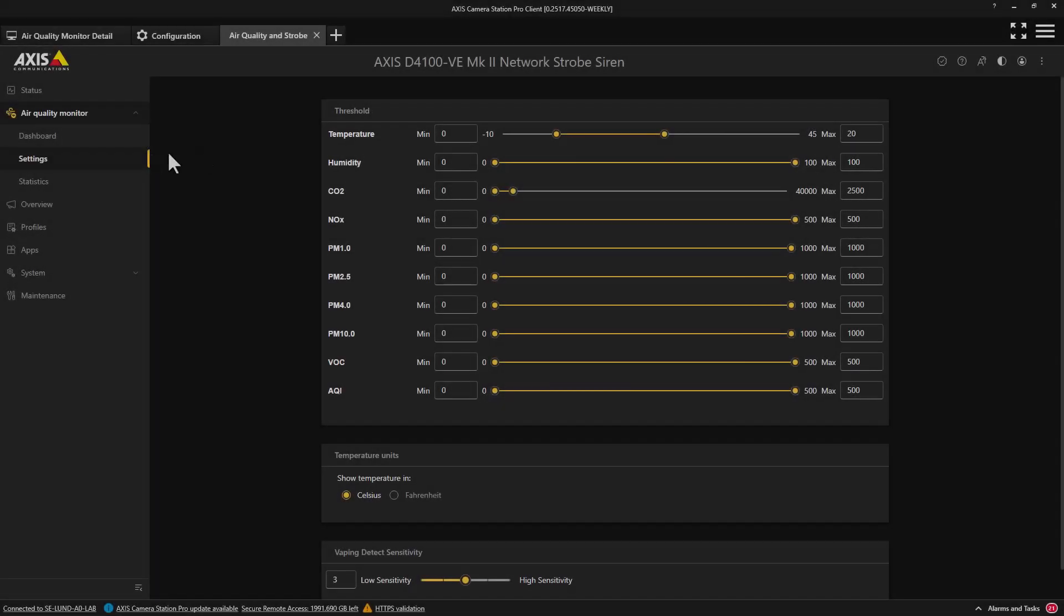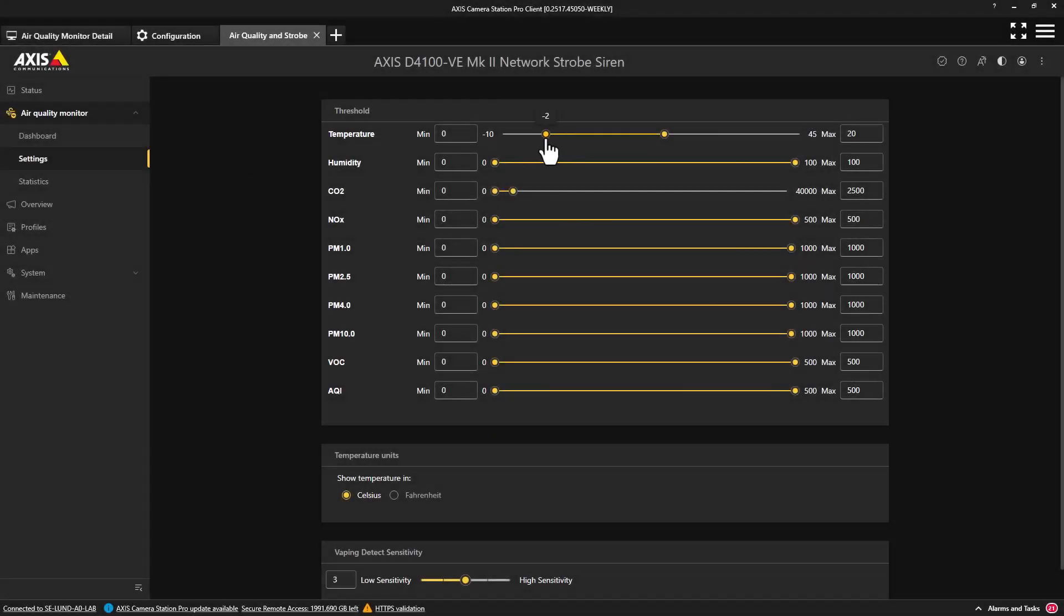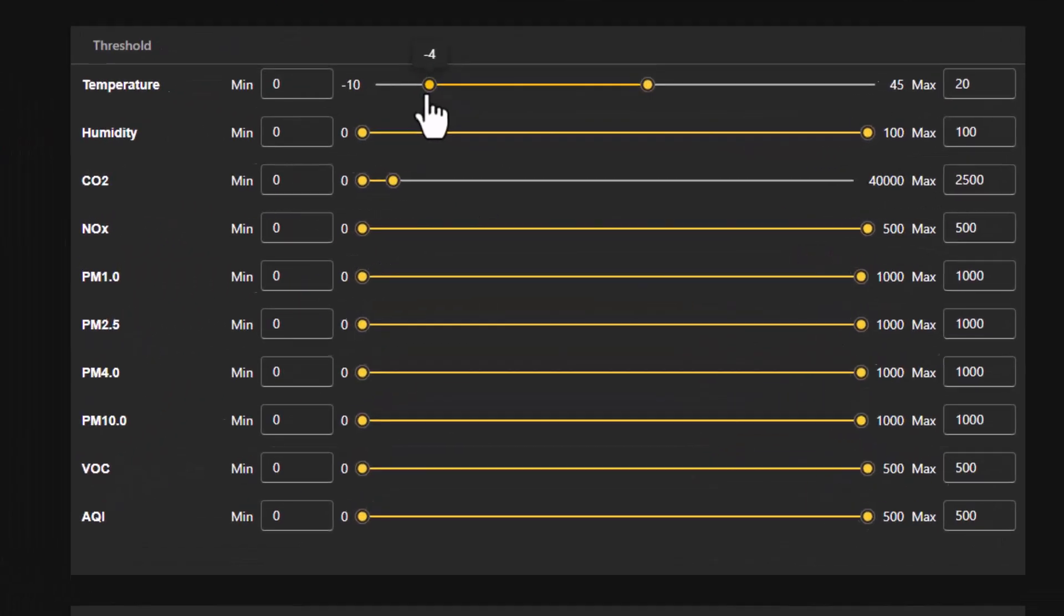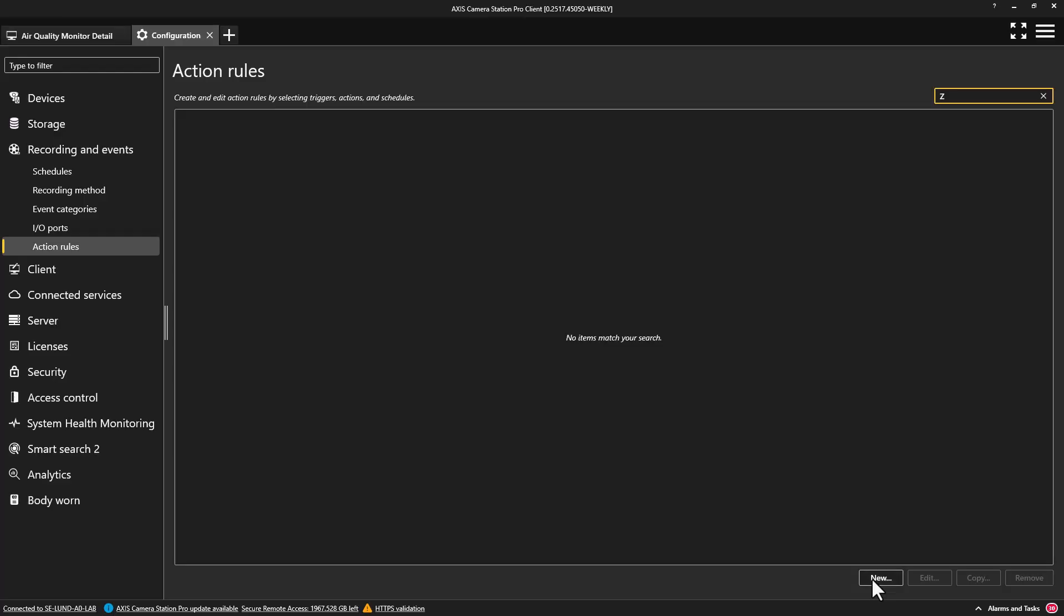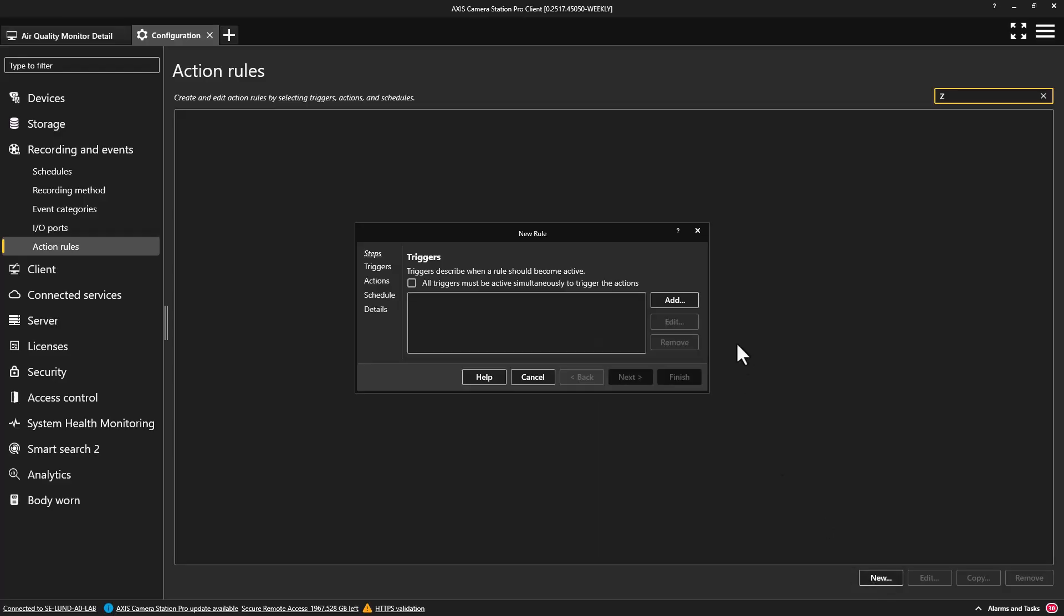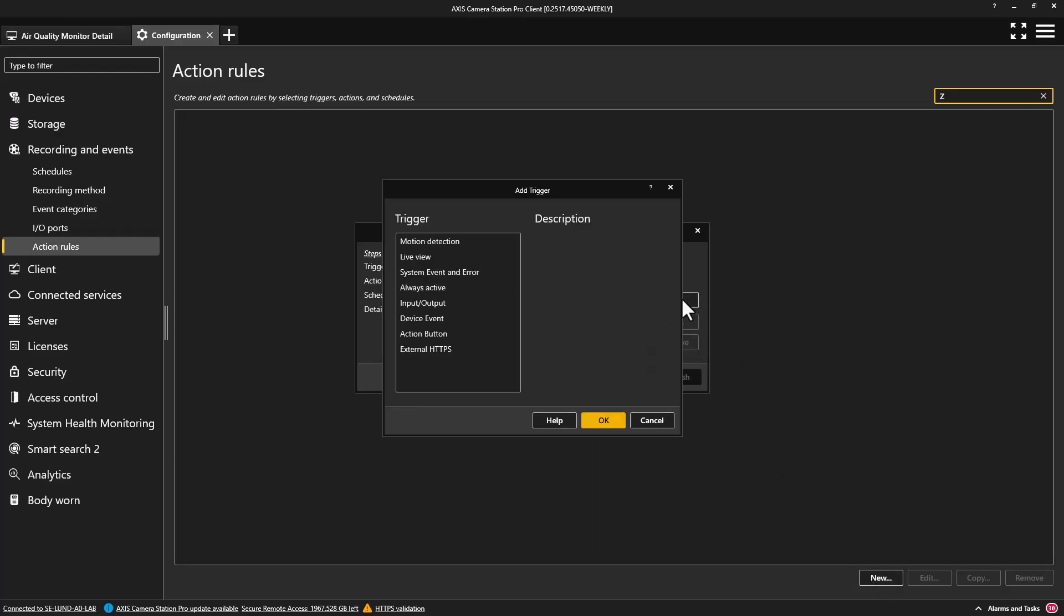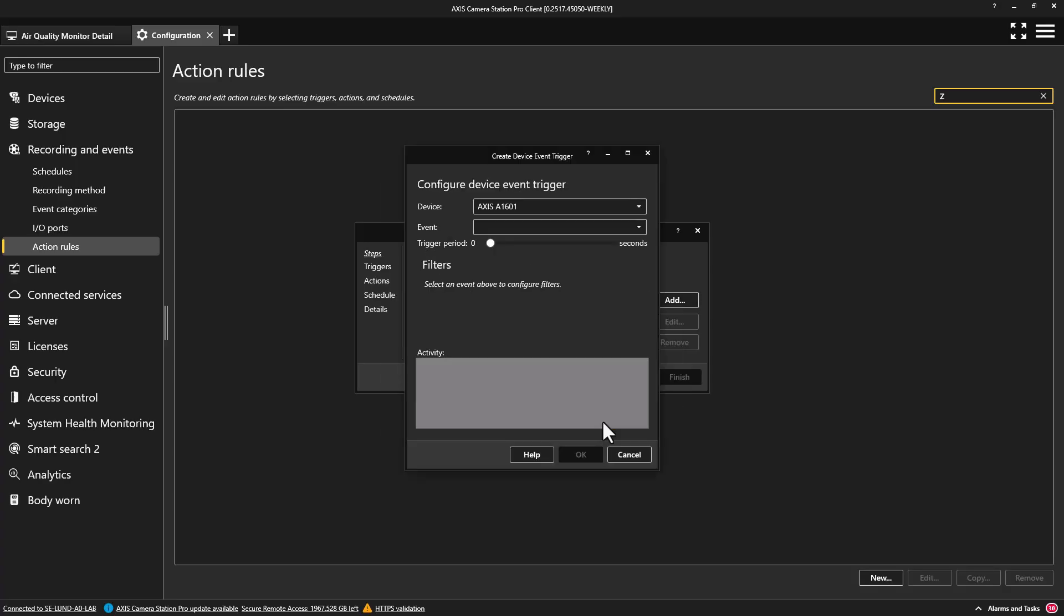Finally, the sensor data can be used to trigger an event when defined thresholds are breached. Within the web interface, thresholds can be set. Action rules can then be created so when those thresholds are reached, an alarm action can be triggered.